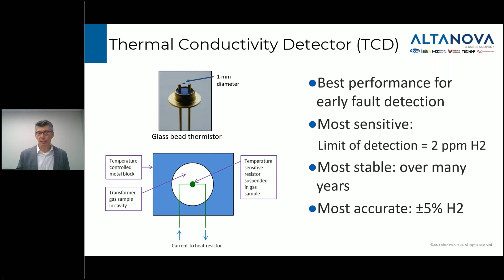And I always like to present a case study or two. So this was a transformer down in Texas. It was coming up on springtime, late in May, and it was warming up outside. Temperatures were rising. If you look at the bottom of the image here, there's a plot of the oil temperature in that transformer over the course of about 2 weeks. Over that time, the daily cycles were modest at first, and then they started growing as everyone was switching on their air conditioning and the transformer was being loaded more heavily during the day.